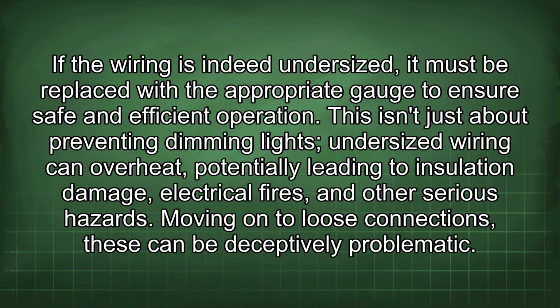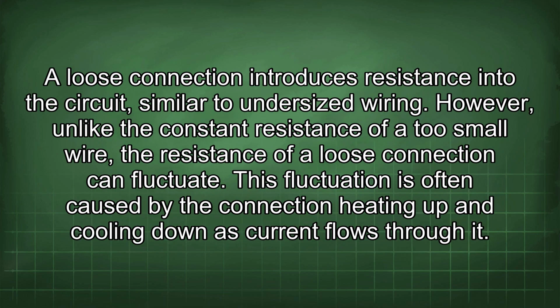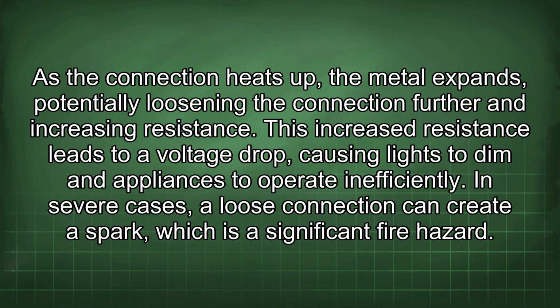Moving on to loose connections, these can be deceptively problematic. A loose connection introduces resistance into the circuit, similar to undersized wiring. However, unlike the constant resistance of a too small wire, the resistance of a loose connection can fluctuate. This fluctuation is often caused by the connection heating up and cooling down as current flows through it. As the connection heats up, the metal expands, potentially loosening the connection further and increasing resistance. This increased resistance leads to a voltage drop, causing lights to dim and appliances to operate inefficiently. In severe cases, a loose connection can create a spark, which is a significant fire hazard.